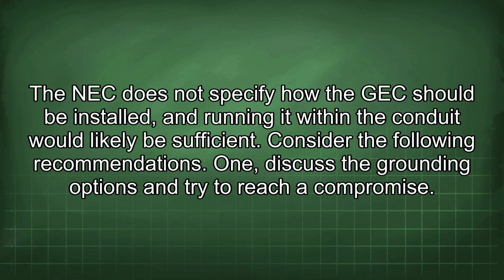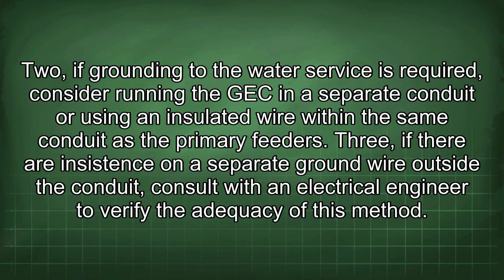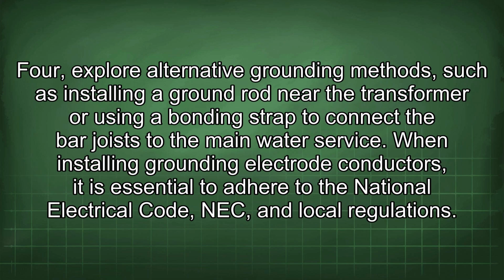Consider the following recommendations. 1. Discuss the grounding options and try to reach a compromise. 2. If grounding to the water service is required, consider running the GEC in a separate conduit or using an insulated wire within the same conduit as the primary feeders. 3. If there is insistence on a separate ground wire outside the conduit, consult with an electrical engineer to verify the adequacy of this method. 4. Explore alternative grounding methods, such as installing a ground rod near the transformer or using a bonding strap to connect the bar joists to the main water service.